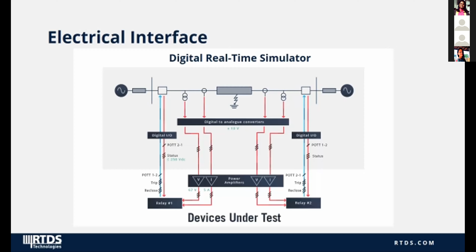Protection testing with digital real-time simulators can also be conducted using an IEC 61850 interface. This is the latest approach in relay testing. The relay can therefore communicate without direct connection to the simulator. Here, the simulator's network interface card allows the simulator to communicate with the physical relay using local area network-based protocols.